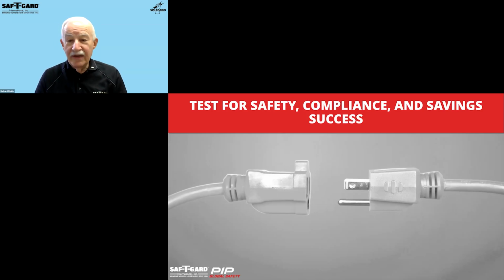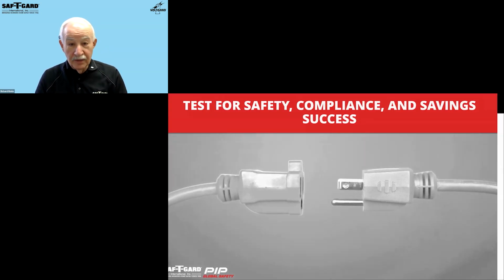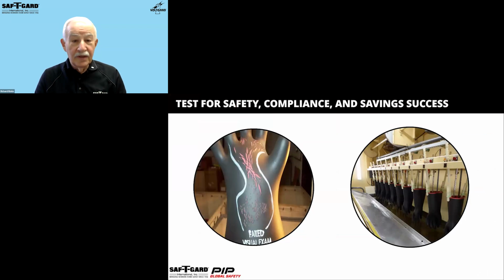Although damage to many types of PPE can be apparent when the equipment or devices are inspected, rubber insulating gloves are more complicated. The reduction in effectiveness can be caused by a variety of factors that may not be readily apparent, as we showed in some of those earlier physical damage examples. So take a look at this one. Rubber insulating gloves damaged by abrasions, scratches, cuts, and snags, as well as sunlight, become apparent when they're inflated.